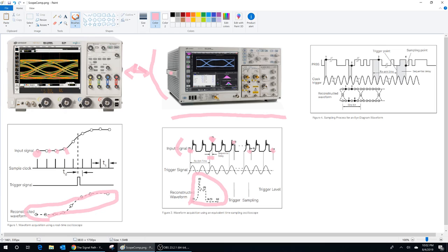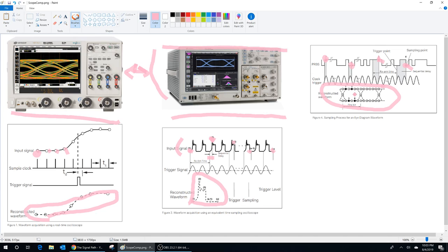Cost is one key difference. The only component that needs 100 GHz of bandwidth is the front-end sampling module; once you take a sample, everything else runs at low frequency — just low-frequency analog processing and a high-resolution ADC. In contrast, a real-time scope requires everything — memory, sample-and-hold, data converter — to run at Nyquist rate, which is much more difficult. You can also construct an eye diagram by subsampling: one dot at a time, reconstructing the eye. Because the timing of the samples is very precise, jitter and ISI are captured accurately, enabling complete eye diagram analysis.